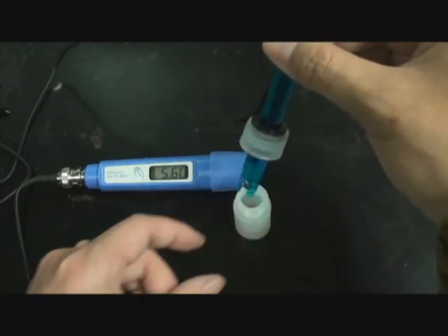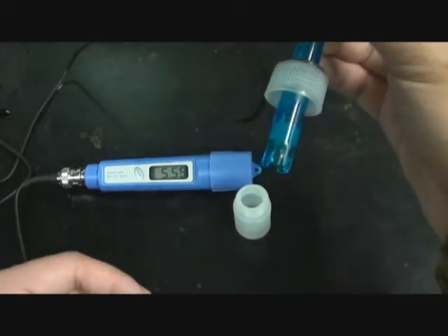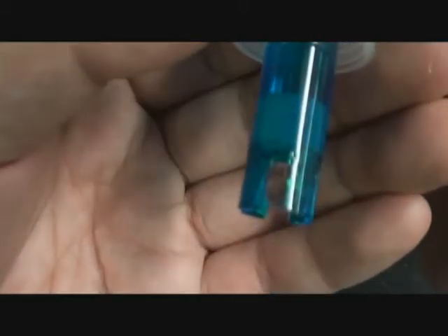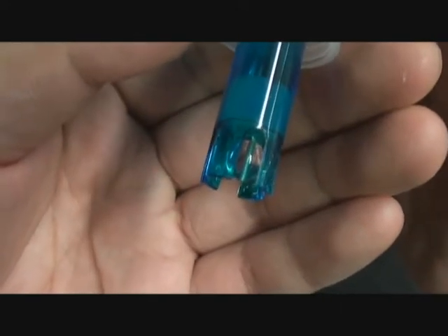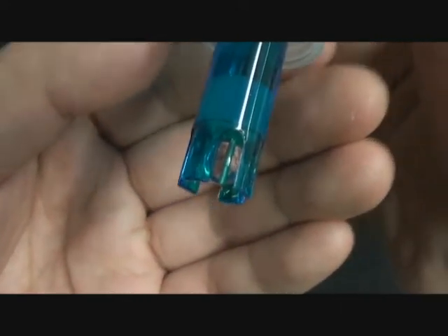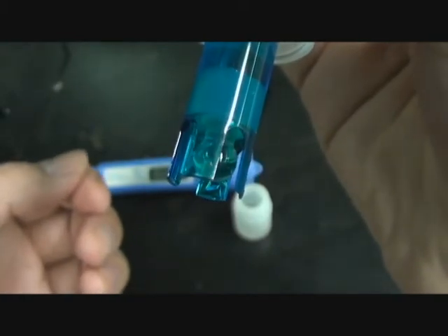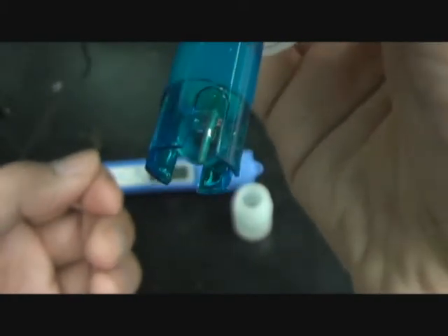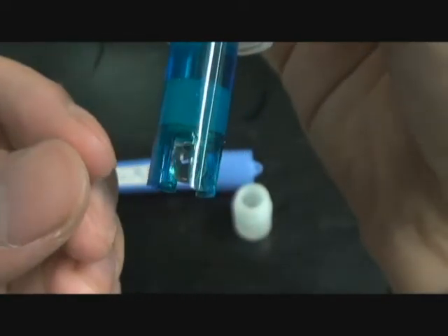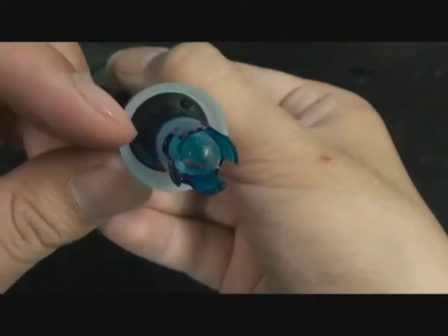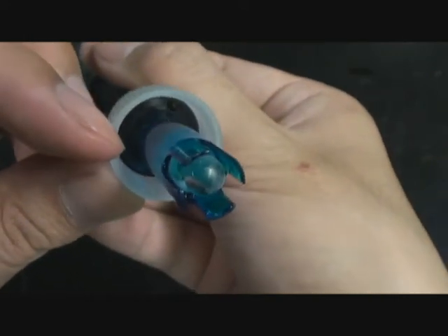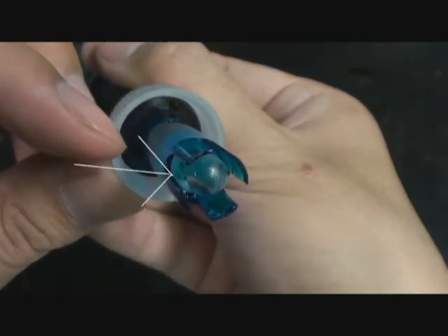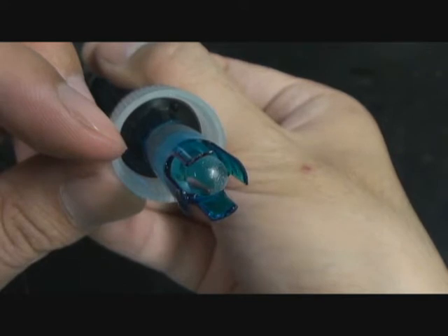Now let me show you the actual glass electrode. And here it is. This glass bulb is what measures pH. If you look inside, there is a metal wire. This wire is the inner reference electrode that measures the potential across the glass. Now, to measure voltage, you need 2 electrodes. So if I can find it here, there it is. Can you see that little nub there? That is the outer reference electrode. This electrode works with the inner reference electrode to measure the potential across the glass and determine the pH.